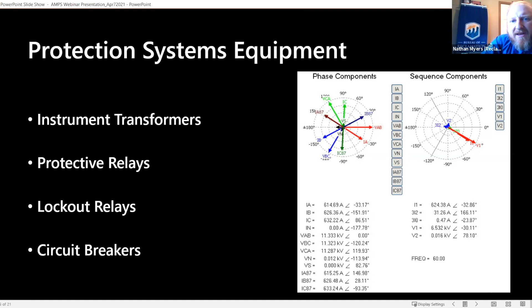As far as instrument transformers are concerned, they look at system currents and voltages that are too high to be directly measured by our protection equipment. So a current transformer can reduce the current values from the system values to a value that can be directly placed into a protective relay. So typically a CT might reduce the overall current from 6,000 amps to a 5 amp signal.